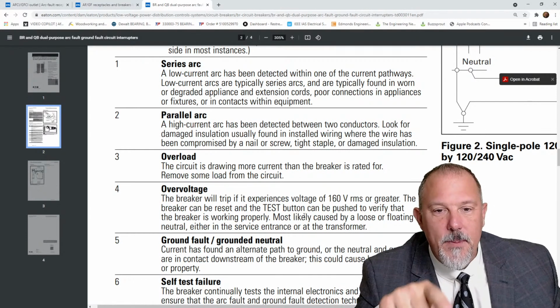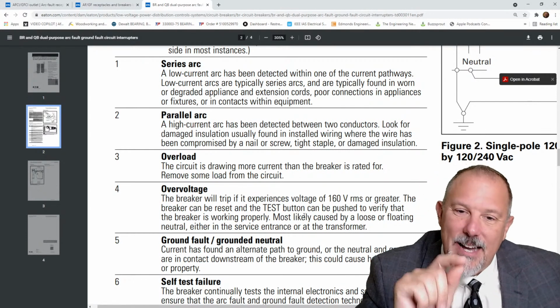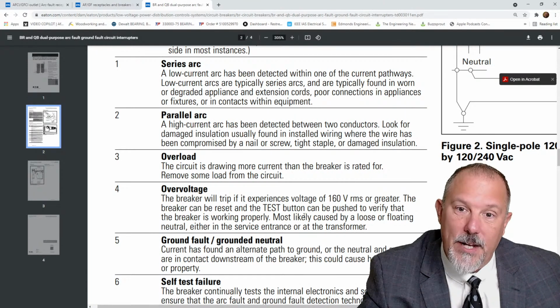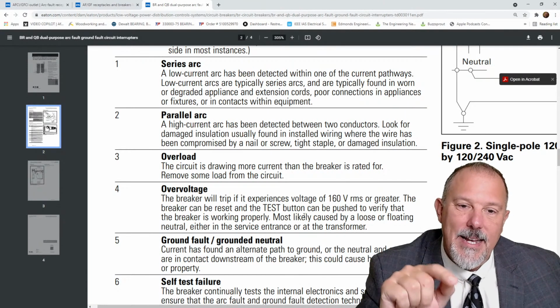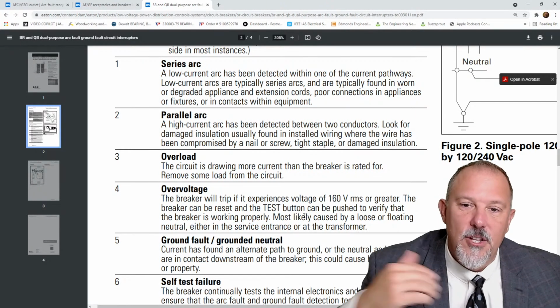The breaker will trip if it experiences voltage of 160 volts RMS or greater. The breaker can be reset and the test button can be pushed to verify that the breaker is working properly, most likely caused by a loose or floating neutral.